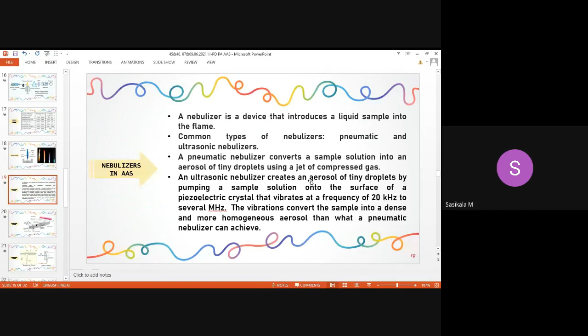There are two kinds of nebulizers, pneumatic and ultrasonic nebulizer. Pneumatic nebulizer functions based on pressure. By means of applied pressure, it will take the liquid sample from the container and pass it into the flame as droplets or in aerosol form. And the ultrasonic nebulizer will give vibrational energy to the sample, whereby it will be converted to droplets and sprayed to the flame. So that is the role of nebulizer.